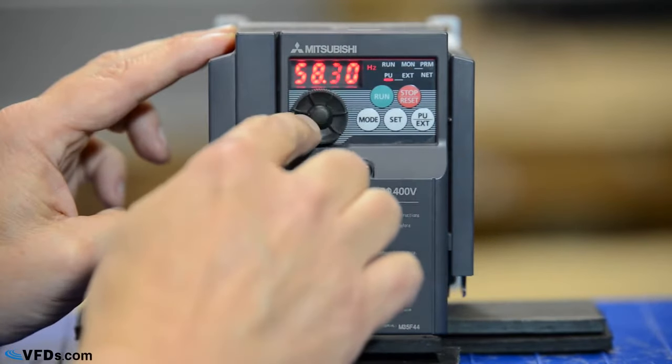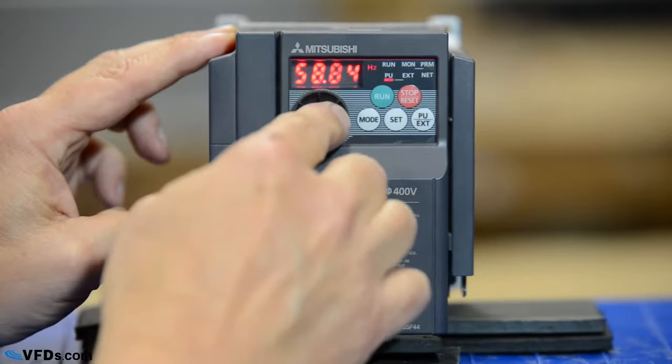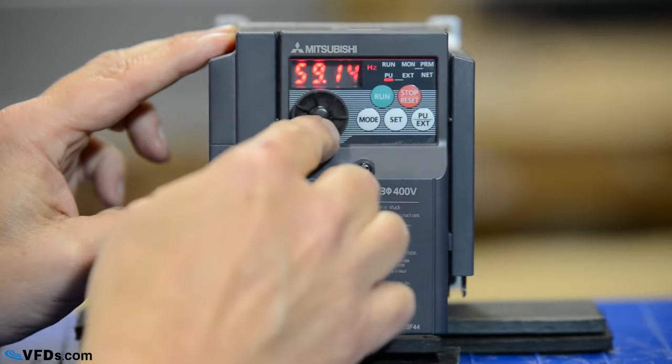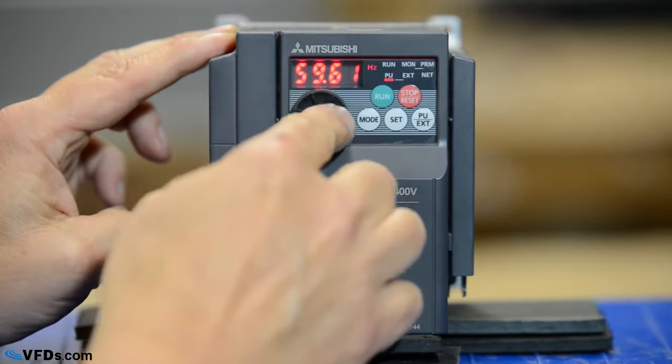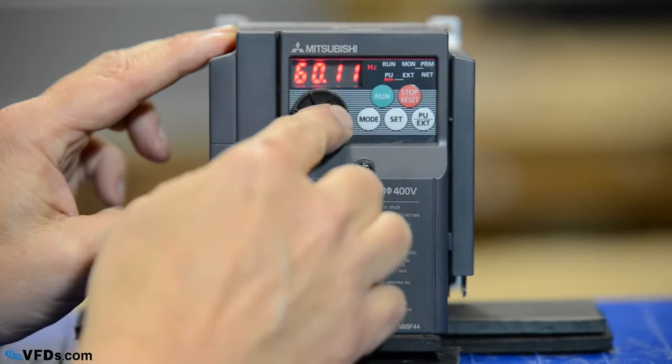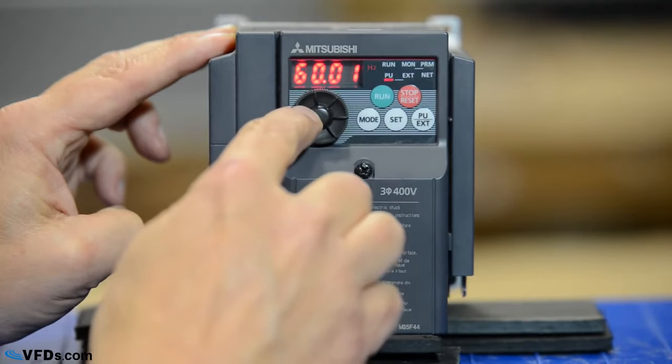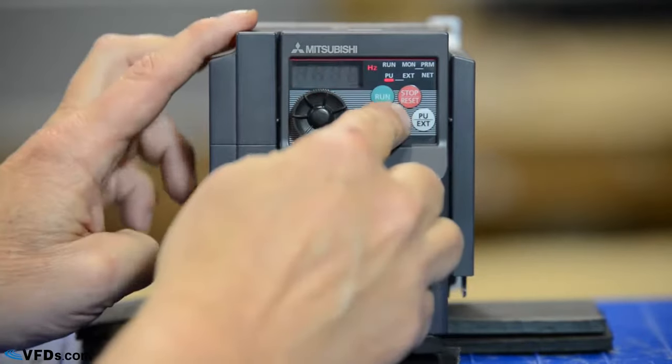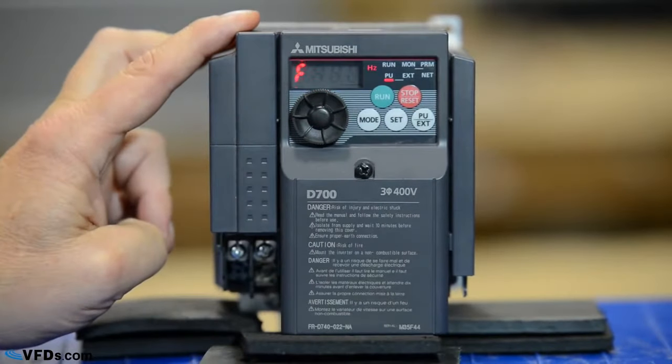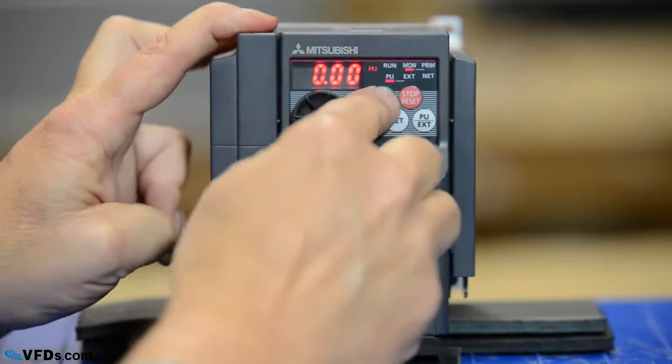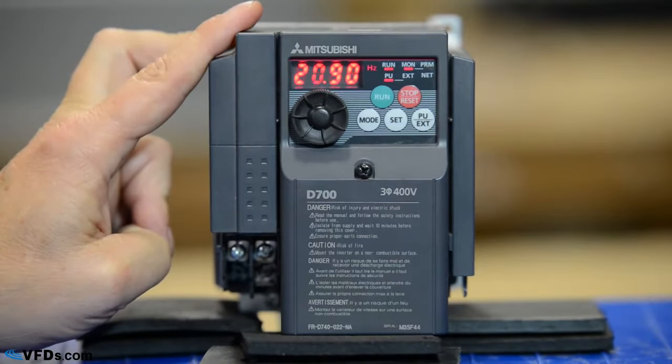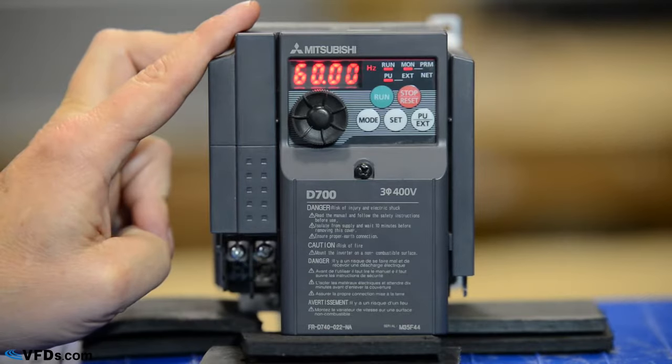Then I'll take this and set a frequency. I'm going to set 60 hertz. I'll move this up to 60 hertz, and when I get to 60 hertz, I'll simply press set and it will seal that in as my running speed. I now simply press run and the drive will ramp up in the programmed acceleration time to 60 hertz.